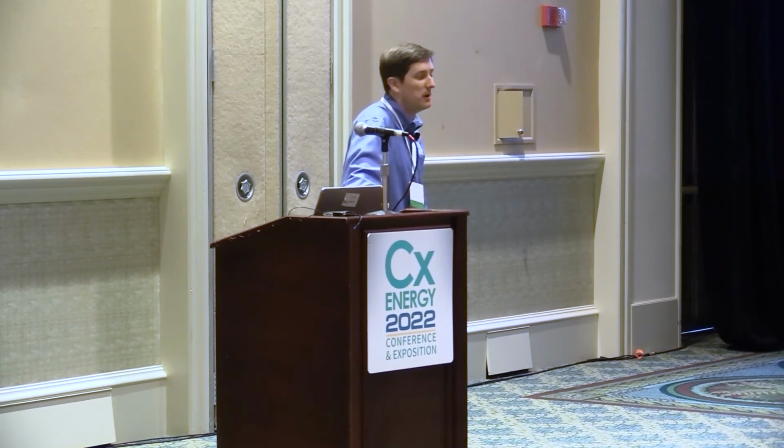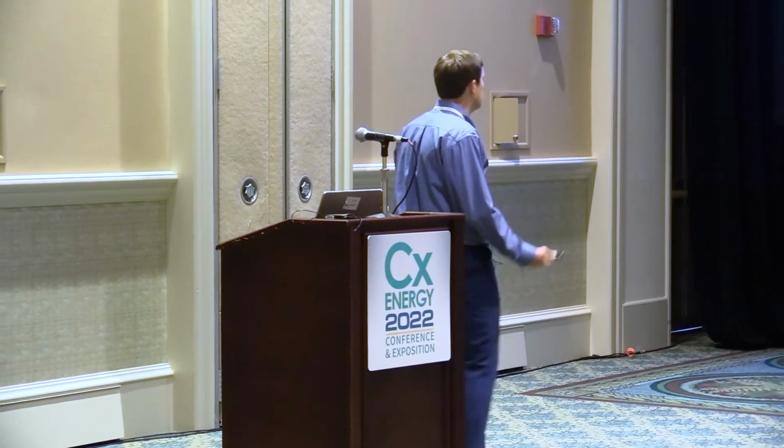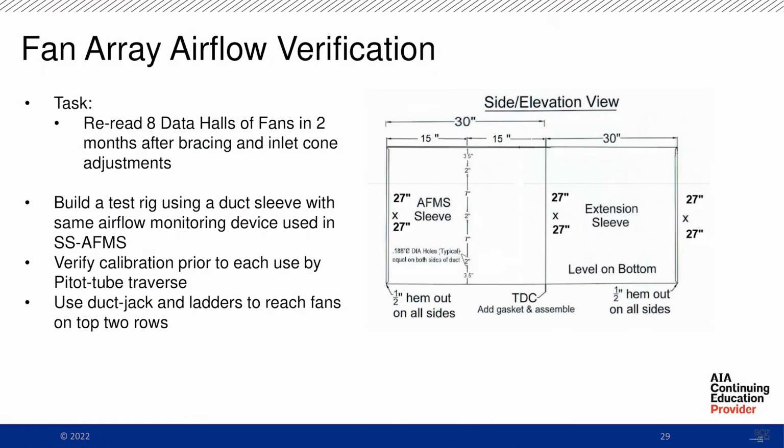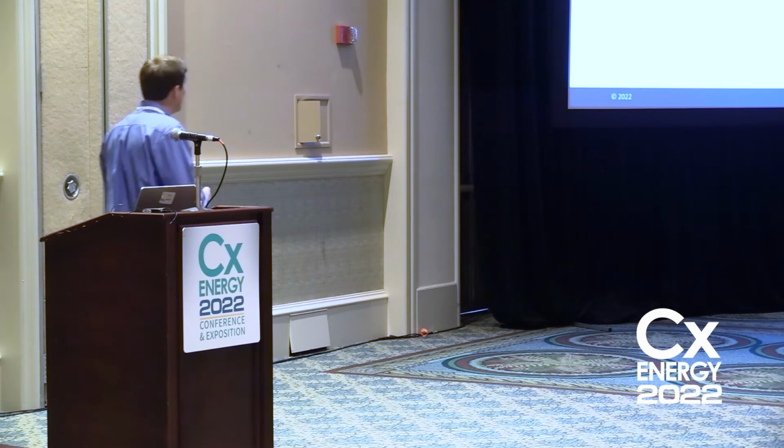I said, well, I don't know. I don't think it's industry standard. He said, no, is it possible, though? Sure, it's possible. We'll see. So we sent this to a sheet metal guy. We have here 2 sleeves that are put together. So when together, it's an airflow monitoring station sleeve and an extension sleeve. 30 inches, airflow monitoring station is right in the middle.